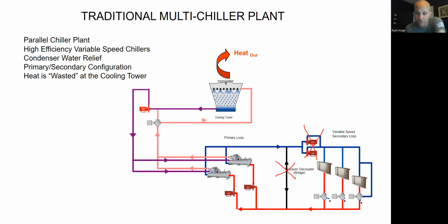And then each of the air handlers or fan coils or radiant ceiling panels or whatever you have, each of those guys has a control valve on them. And the thermostat for that zone or the building automation system for that zone is going to open and close that valve more or less to allow more chilled water to flow through the coil to cool and dehumidify that air. And then typically the last zone will have a three-way valve. So these guys are two-way, this guy's three-way. The reason being is these are variable speed loops and they're going to control the pressure sensor. If this guy shut off completely, there'd be no flow through that loop and the pressure sensor wouldn't be doing a very good job. So a lot of times we'll have a little bypass loop at the end, just so we have enough flow through the total loop that we can measure something. All right, that should be the chilled water side.